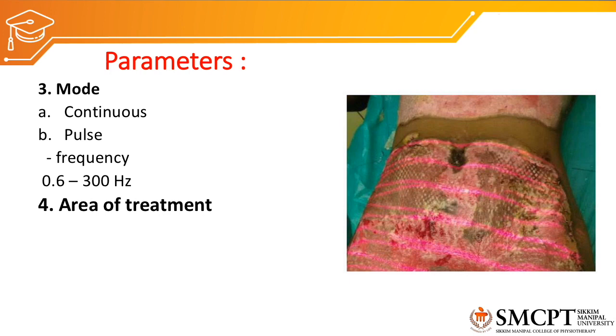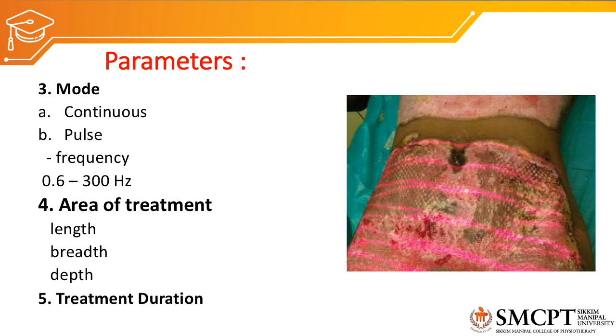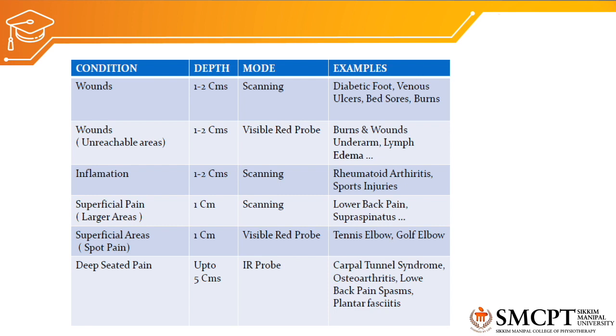The next parameter is the area of treatment — the length, breadth, and depth of the wound or tissue that requires laser therapy. These dimensions are entered by the therapist, and after all parameters are selected and entered, the machine will automatically calculate the treatment duration.